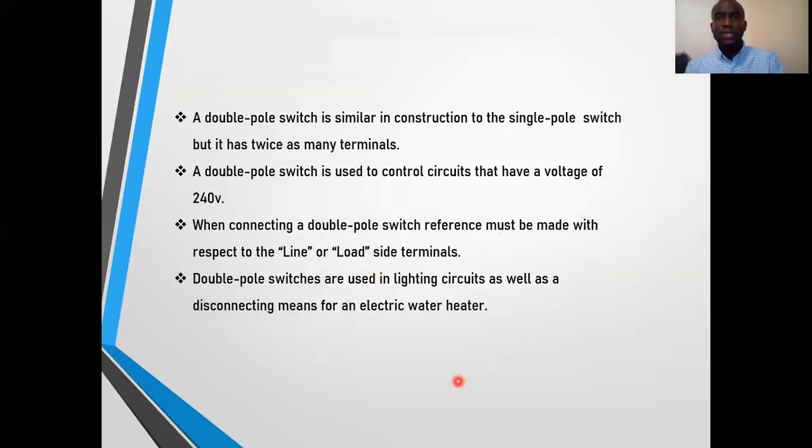A double-pole switch is similar in construction to the single-pole switch, but it has twice as many terminals. A double-pole switch is used to control circuits that have a voltage of 240 volts. When connecting a double-pole switch, reference must be made with respect to line or load side terminals. Because, as we say, this switch has a single throw, but two contacts are being operated at the same time. So if you have any crossing between line and load, the switch will not work properly. Double-pole switches are used in lighting circuits for those large lights that require 240 volts, as well as a disconnecting means for an electric water heater.